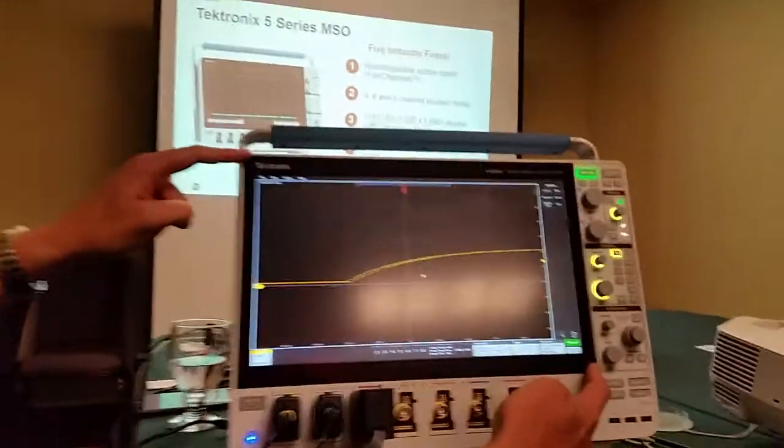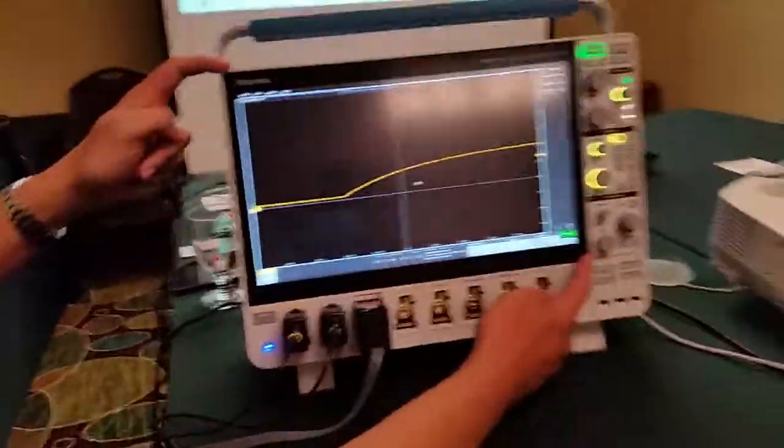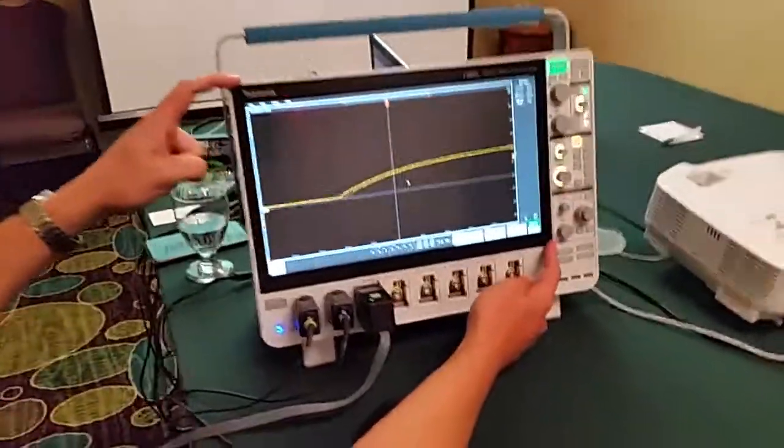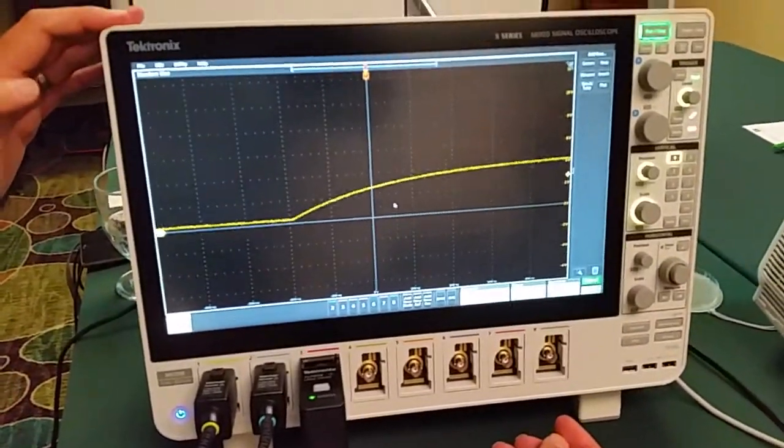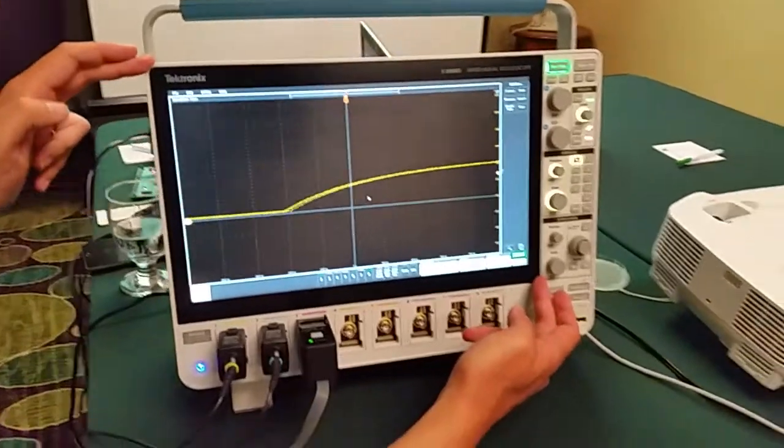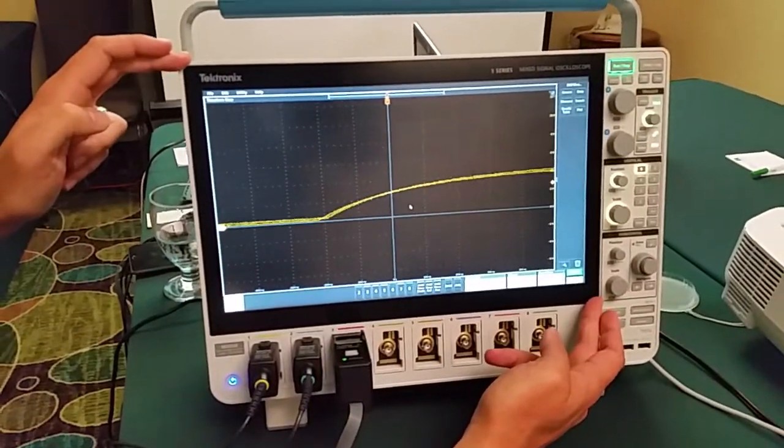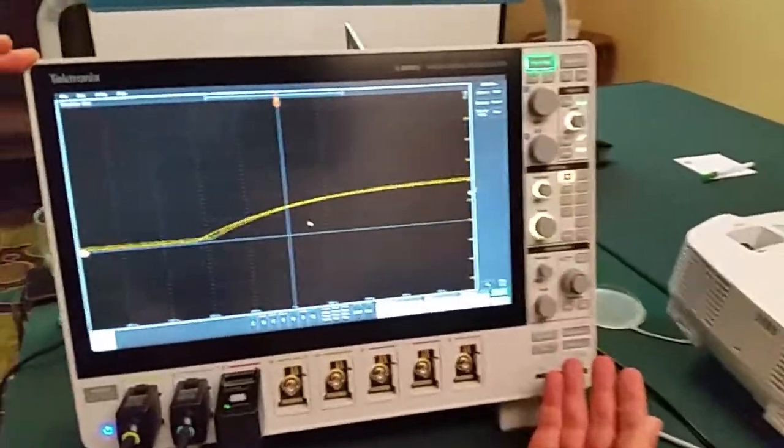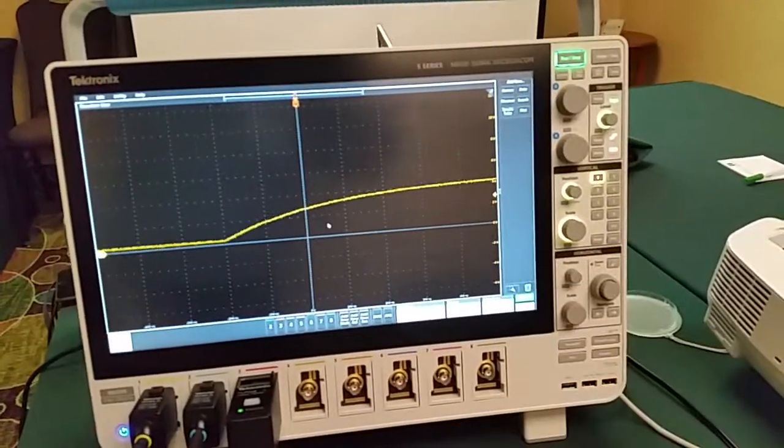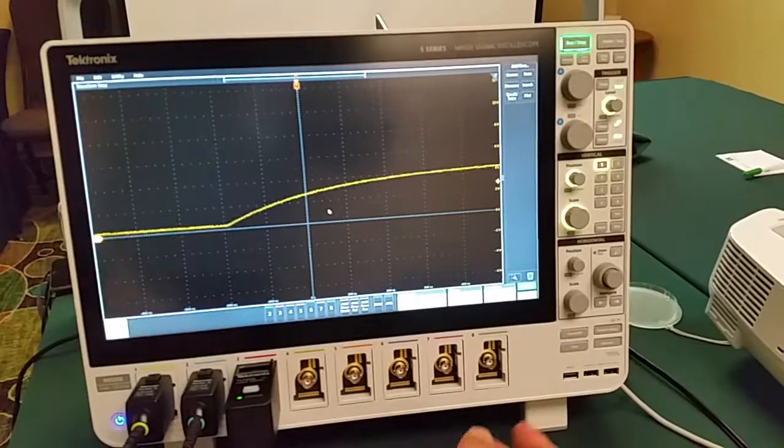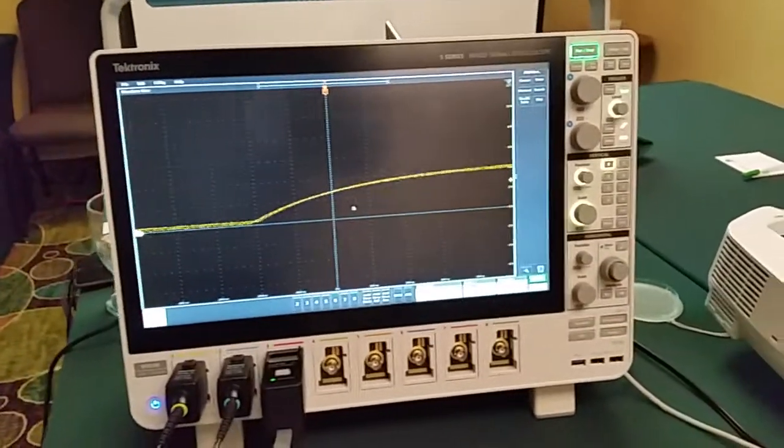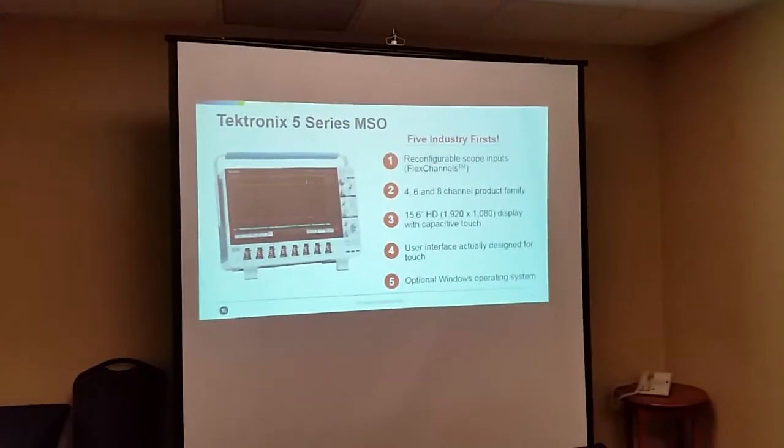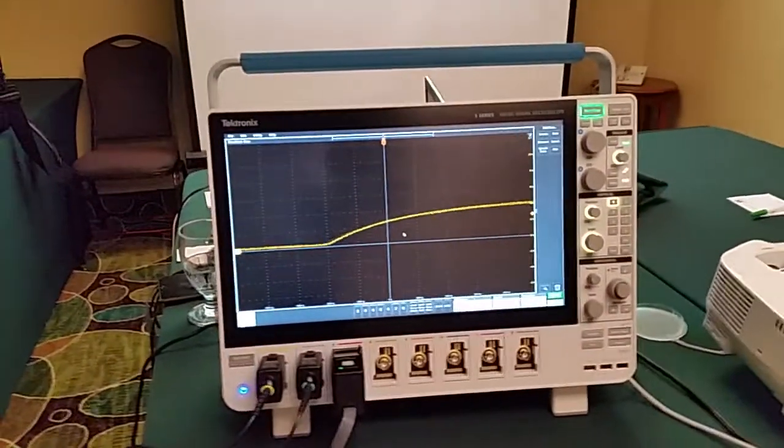Fantastic 15.6 inch HD display. Full HD, 1024 by 1920 by 1080 with capacitive touch. We'll run through that in just a minute here. Next, just how impressive the display is, it actually takes up about 85% of the front face of the instrument. 15% consumed with the front panel here, which still retains the critical controls necessary for driving the scope. Many things have been moved into the user interface, which you'll see in a minute here in the demonstration. It's the first user interface actually designed for touch, and the instrument has an optional Windows operating system.